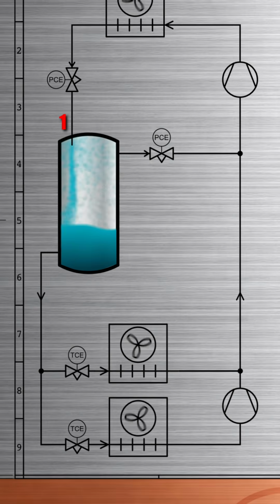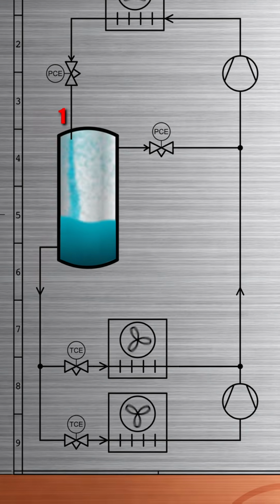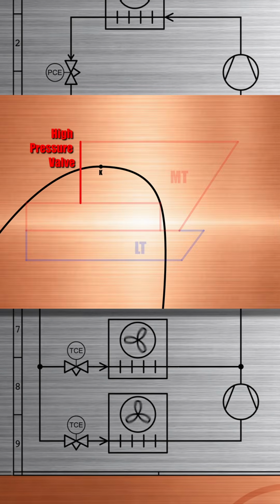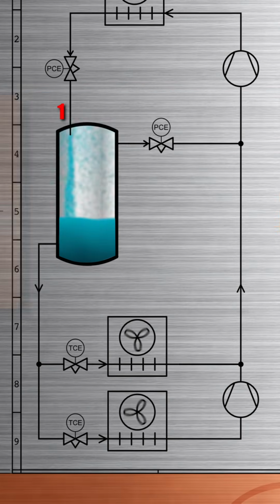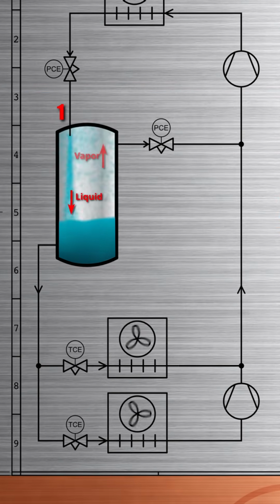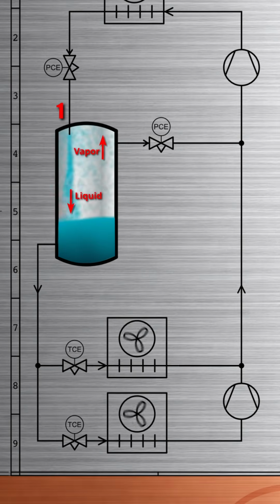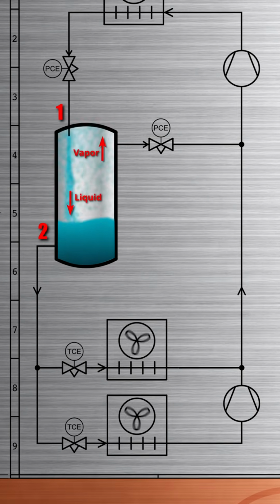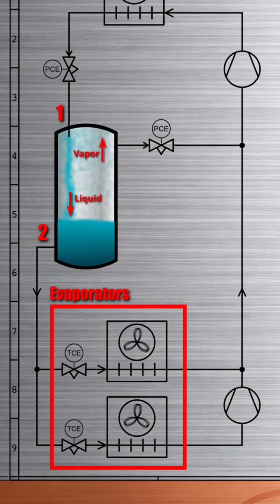Through the first port, the high pressure valve injects into the receiver. Due to throttling, the CO2 undergoes a phase change into wet vapor. Inside the receiver, the wet vapor separates and the liquid state collects at the bottom. With the second port, the refrigerant units are supplied with that liquid.